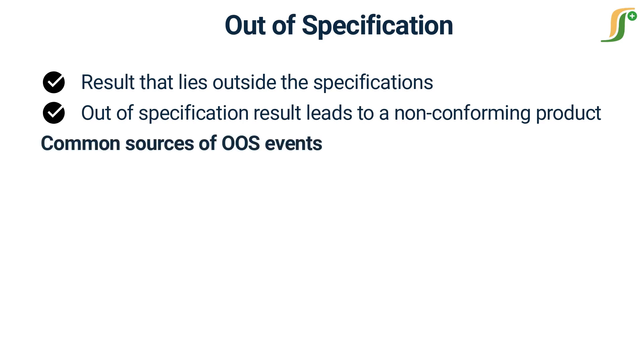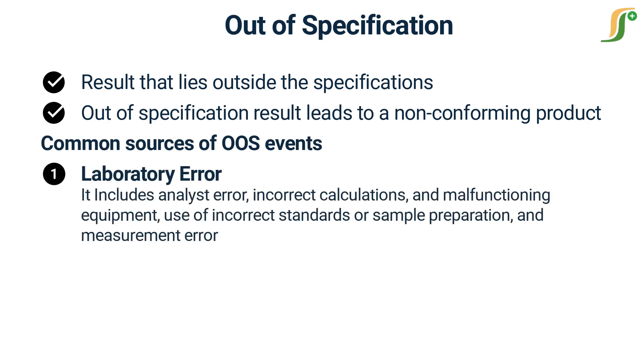Here are common sources of OOS events. The first source is laboratory error. Types of laboratory errors include analyst error, incorrect calculations, malfunctioning equipment, use of incorrect standards or sample preparation, and measurement error. Confirmation that this was the cause of the OOS condition would not constitute a product failure.